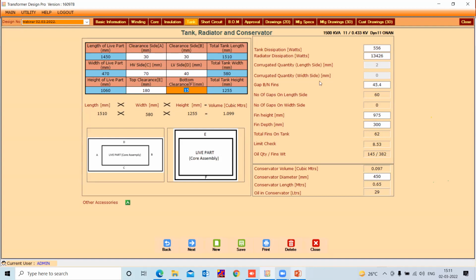Now let's see the right hand side table. There is a tank dissipation, radiator dissipation, corrugated quantity. Now we have selected corrugated types. That's why you will get the information about all corrugations and the corrugation tank. If you select another type of radiator, you will get a different kind of information over here based on the tank and radiator type selected on the basic information page. Now we have selected corrugated fins. So let's see the gap between fins, which can be editable, the number of gaps on length side, width side, fin height, fin depth. Here also, all cells with white background are editable, and that will impact your total number of fins.